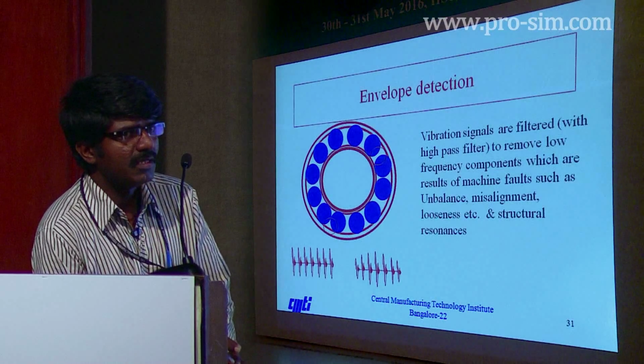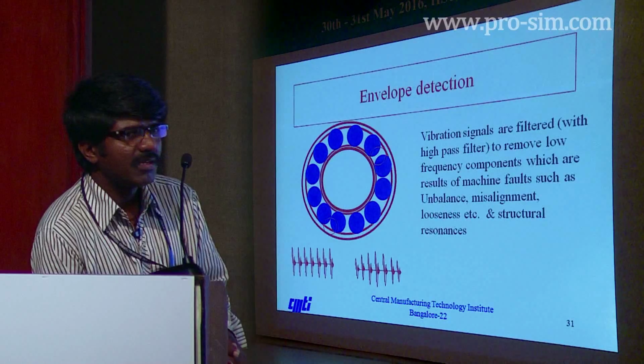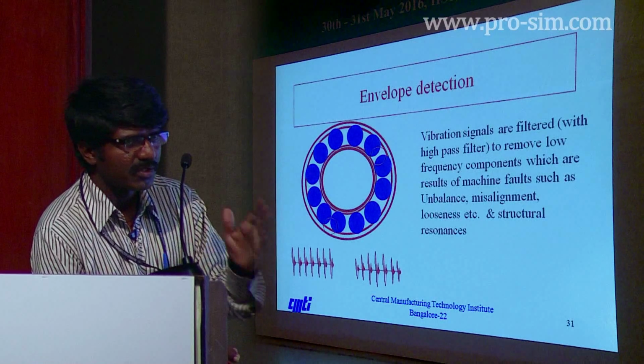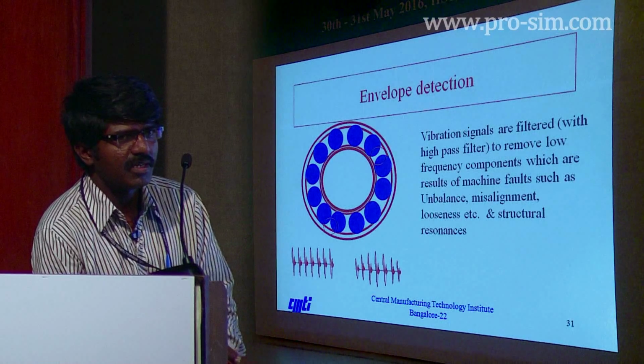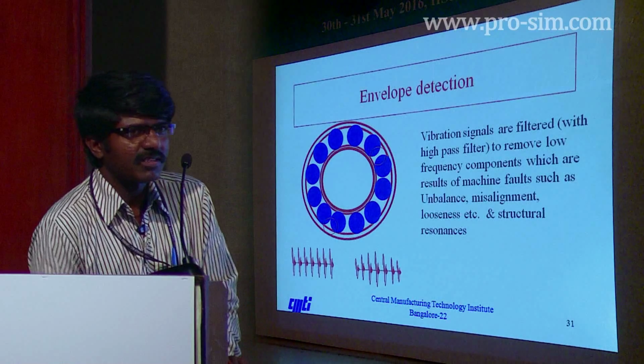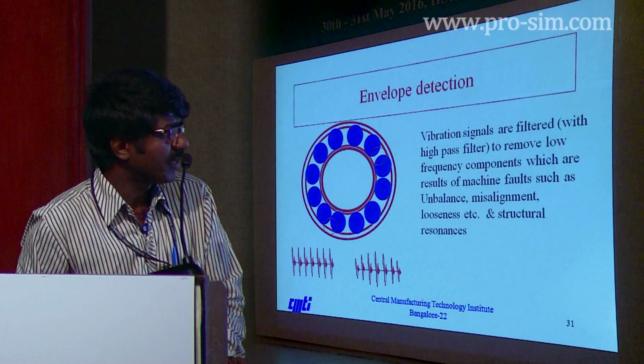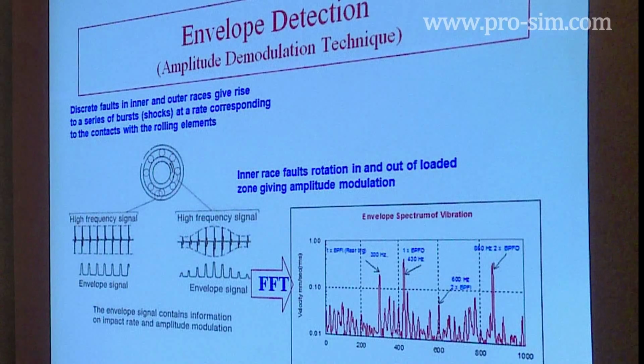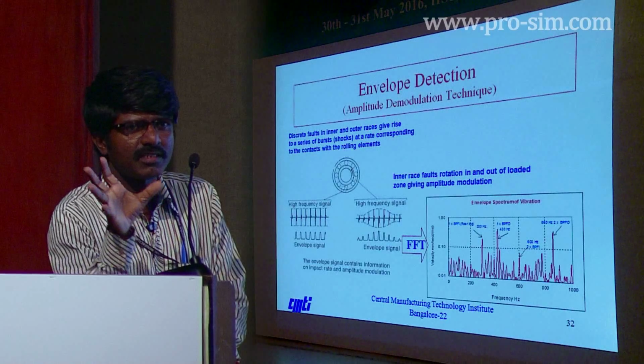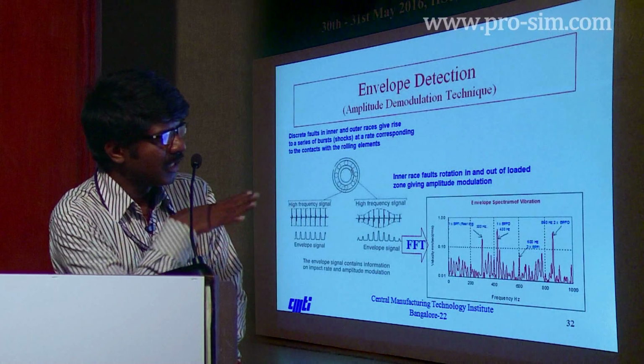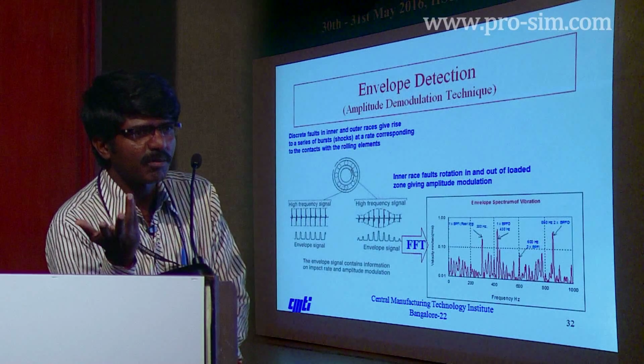Envelope detection means it does amplitude demodulation. They pass the signal through a high pass filter and extract only the bearing defects and the gear faults related frequencies. Once you do the amplitude demodulation, you will get the envelope spectrum where bearing fault related frequencies will be enhanced. Otherwise, you don't see these bearing defect frequencies in the normal spectrum. Okay.